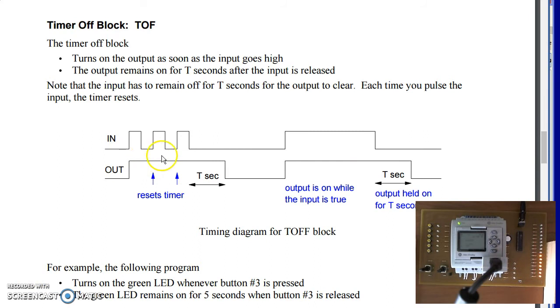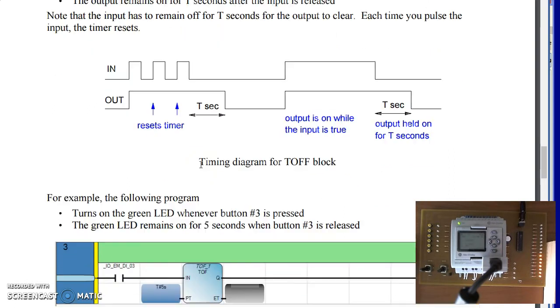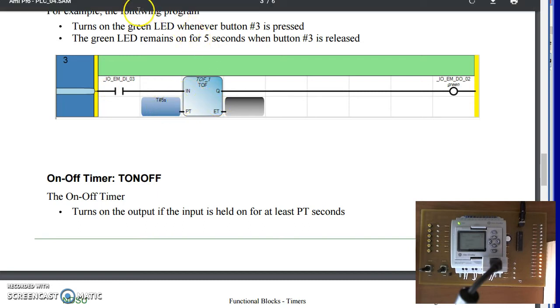The T off block holds the output on for T off seconds. For example, when you turn off the light switch in the bathroom, you might want to leave the fan running for 30 seconds afterwards to remove the humidity. That looks like the following. It will turn on with the rising edge and remain on for 5 seconds after I release the button.